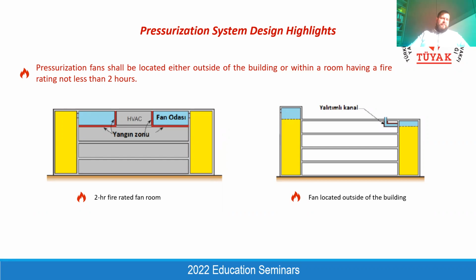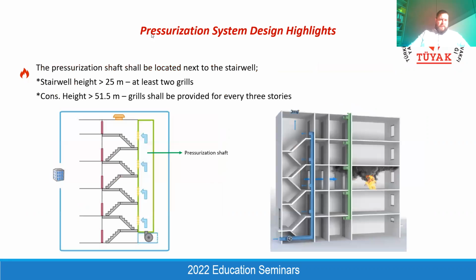Because just for your information, the pressurization shaft is considered a part of the staircase. When we design a staircase, the design criteria are exactly the same for the pressurization shaft as well. That's why it's really important for us. The pressurization shaft shall be designed and constructed very carefully, because any deficiency within the pressurization shaft will block the fire escape stair, and the people cannot evacuate the building because of this deficiency.